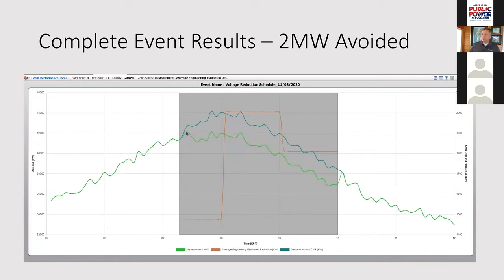The voltage was reduced progressively as much as possible without causing violations, based on feedback from the meters. The light green line at the bottom represents our actual flow; the darker green line is what we would have been. There's no magic trick to the difference—it's actually V equals IR, fairly simple and reliable, to say that really was a savings of this much power.